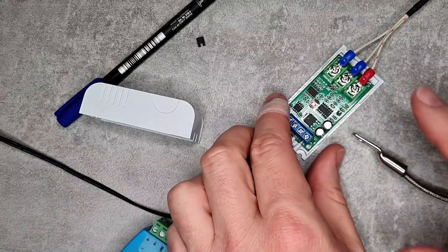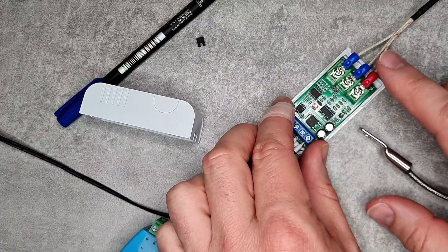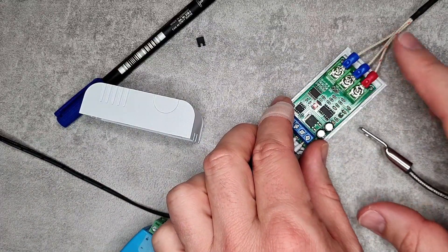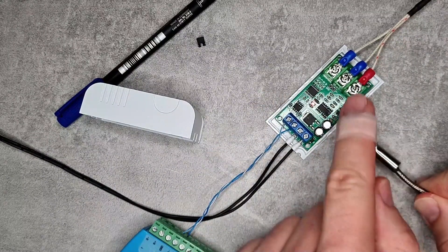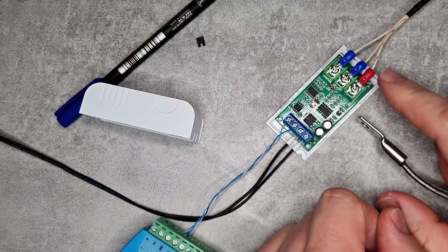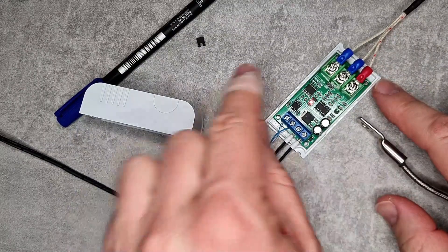As you can see, you connect the three wires here. If you have a three-wire temperature probe, you wire the wires like this one. Also there's a jumper here, so if you're using a three-wire version then you remove the jumper.